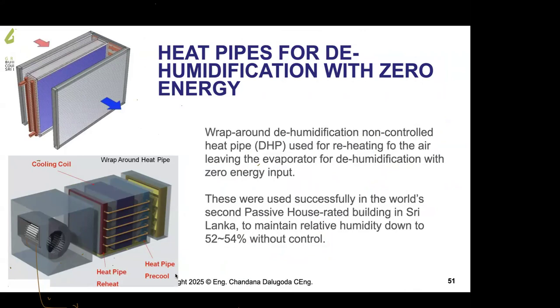Another way is heat pipes for dehumidification with zero energy. Zero energy, mind you. What is dehumidification? See, in comfort air conditioning systems, RH will have to be kept at 60% and below. The usual norm is 50 to 60%. But in Sri Lanka, we can manage 55% to 60%. Sometimes, by nature of the system, or rather application, relative humidity increases. Our design is 60 and below, but your calculation, the simulation, shows you are at 65% RH.